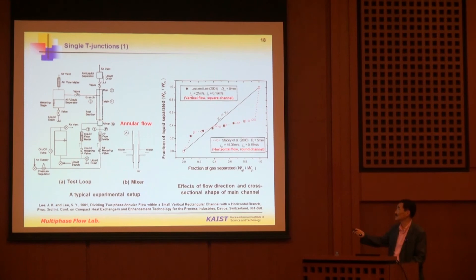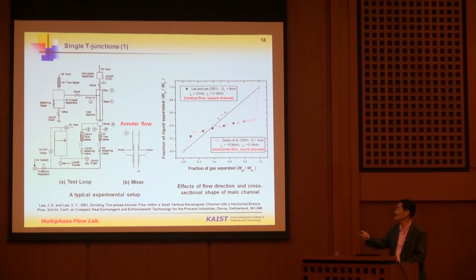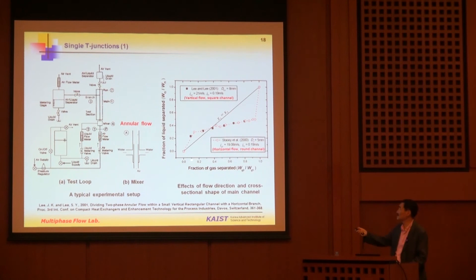Flow goes to the run and branch, and we control valves on the run side and valves on the branch side. If you open the valve a little more on the run side and reduce the opening on the branch side, the pressure at the junction remains the same. You can thus control how much flow goes out to the branch or to the run.